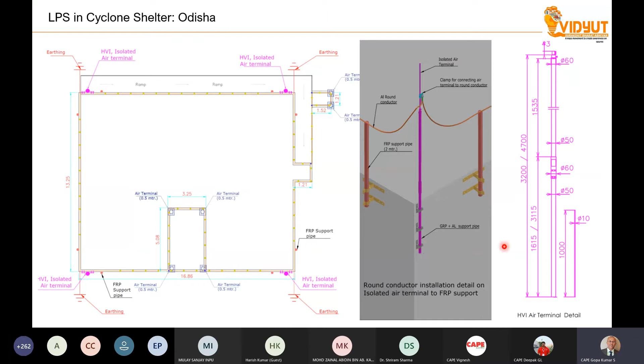As a result, there was a big tender. It is a cyclone shelter. If we make a risk assessment, probably no lightning protection is required for this building. Even if it is required, probably lightning protection level 4. The drawing looks like an LPS for a high security explosive storage building. The terms used look like products from Europe were selected. It is an internationally funded project. The estimate, I am sure, is between 15 to 20 crores.